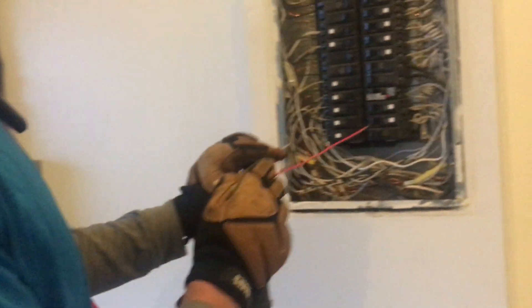This is probably the 14th house I've done in the last seven years, so I'm not scared of working on them. I think they're fun to trace out. There are a lot of key tricks I've used. I've been criticized for using a light bulb to check for voltage, but that's not what I'm doing here. This light bulb is really a great tool. If you're trying to figure out if your arc fault is working — look at that, it is. I'm putting a load on it.